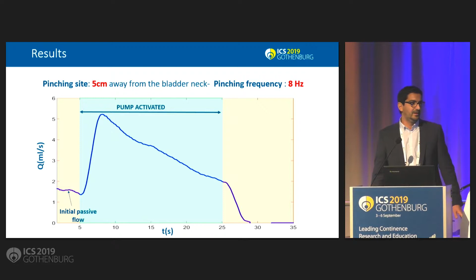This is how a typical waveform looks. In the beginning, we have some initial passive flow, because we fill the bladder with 120 milliliters of water. But as you can see in the green region, as soon as we activate our pump, we see a steep increase of the flow, reaching a maximum, in this case, close to 5 milliliters per second. That was followed by a decay. What was more important is that we could always reach complete bladder emptying within a few minutes.